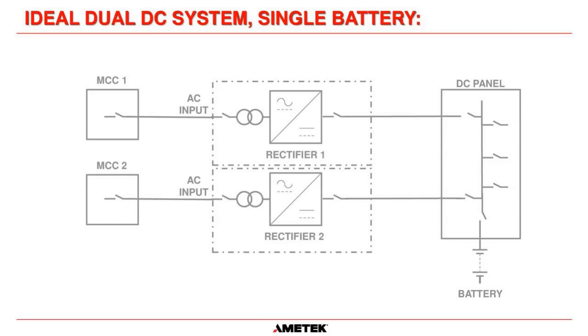So in truth, this drawing here is one of the absolute best designs you can have. This is a dual redundant charger system, and you can see that charger 1, rectifier 1, is fed from MCC1 from its own bucket, and rectifier 2 is fed from a separate MCC. So it's giving you possibilities now, because obviously if somebody is going to do maintenance on MCC1, then MCC2 is going to remain powered and can continue to power your DC circuits through rectifier 2. So this gives us some redundancy.